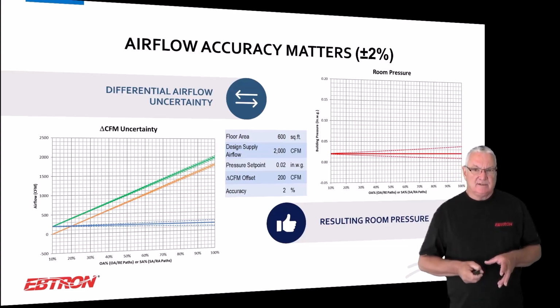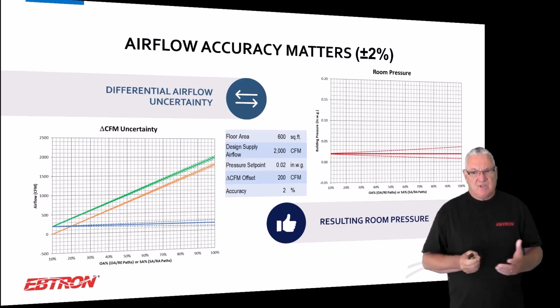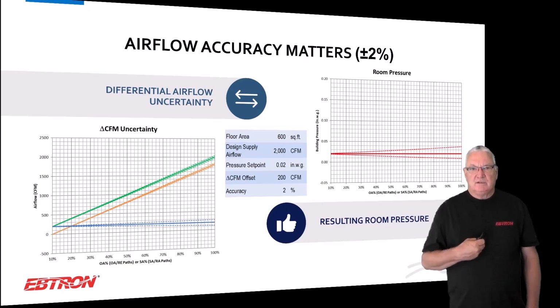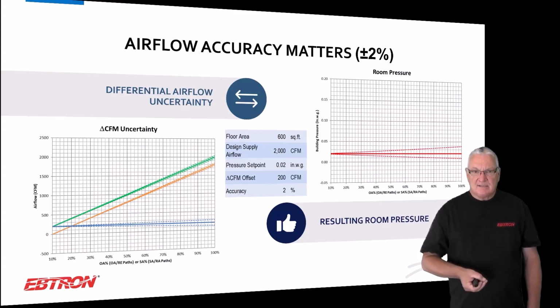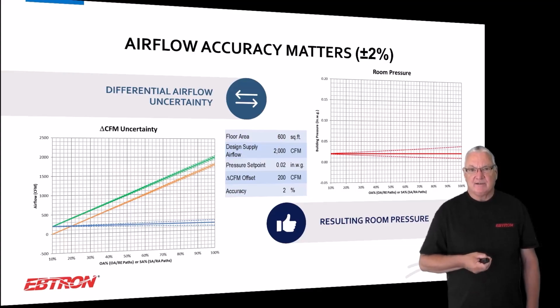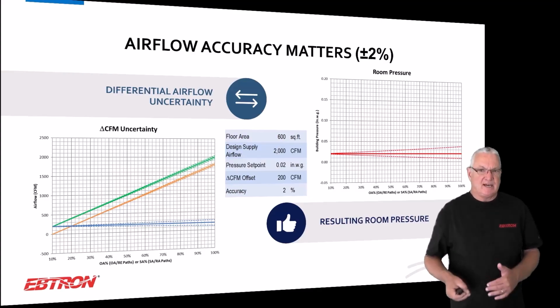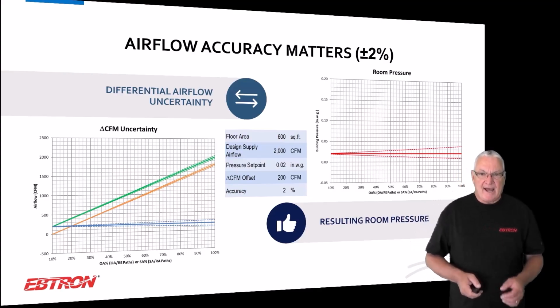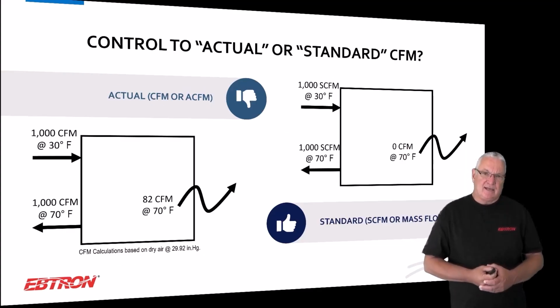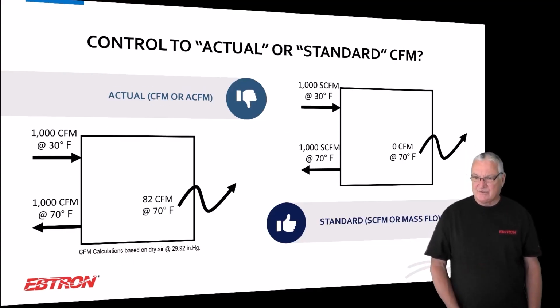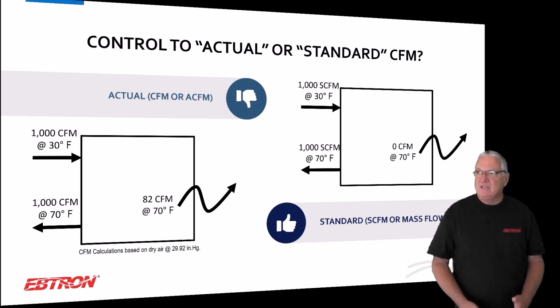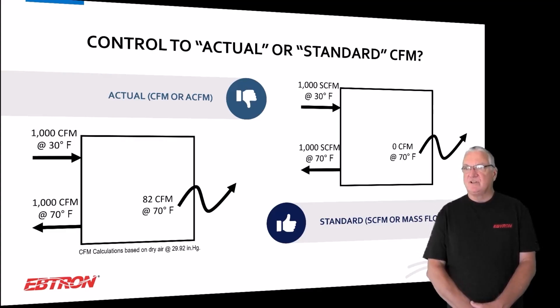Accuracy really does matter. In fact, I can show you cases where even our flow meter, properly installed, out of the box, even if it was 2% accurate, isn't accurate enough. So we're going to talk about that a little bit more at the end when we talk about technology and things we can do there, all right? But accuracy does matter. The other thing that I think matters, that our industry is kind of in the dark ages about, is that everything we seem to do in HVAC is based on actual flow, actual CFM, based on velocity, linear velocity.